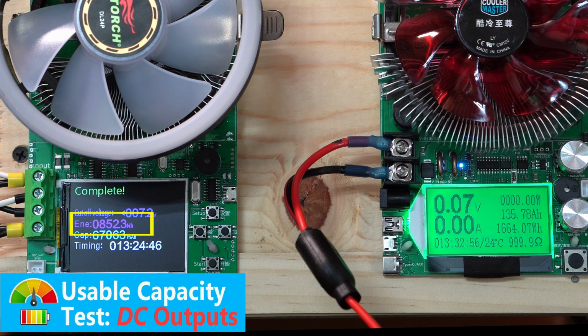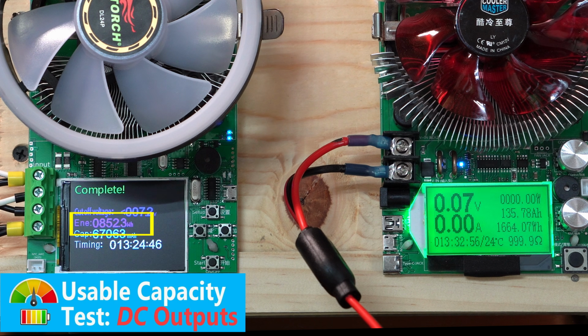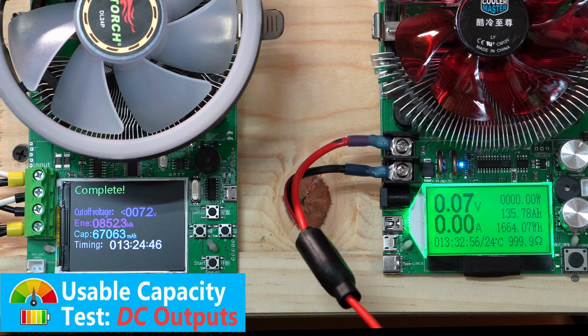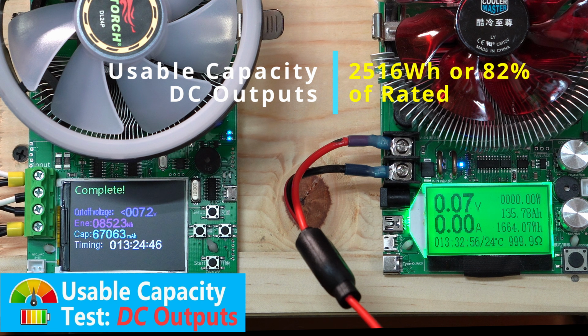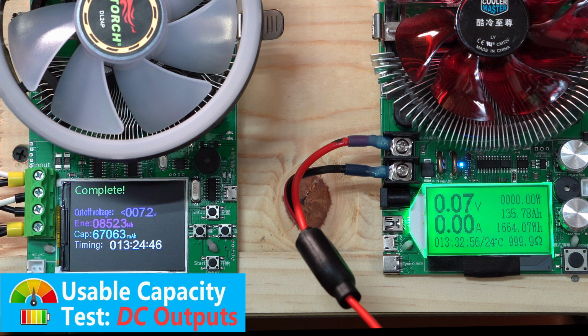On the tester on the left, we got 852 watt hours, and on the tester on the right we got 1,664 watt hours. Combined that gives us 2,516 watt hours, out of a rated 3,072. That puts us right at about 82% of rated capacity through the DC ports — slightly on the bottom half of average, but squarely in the average range of 80 to 85%.